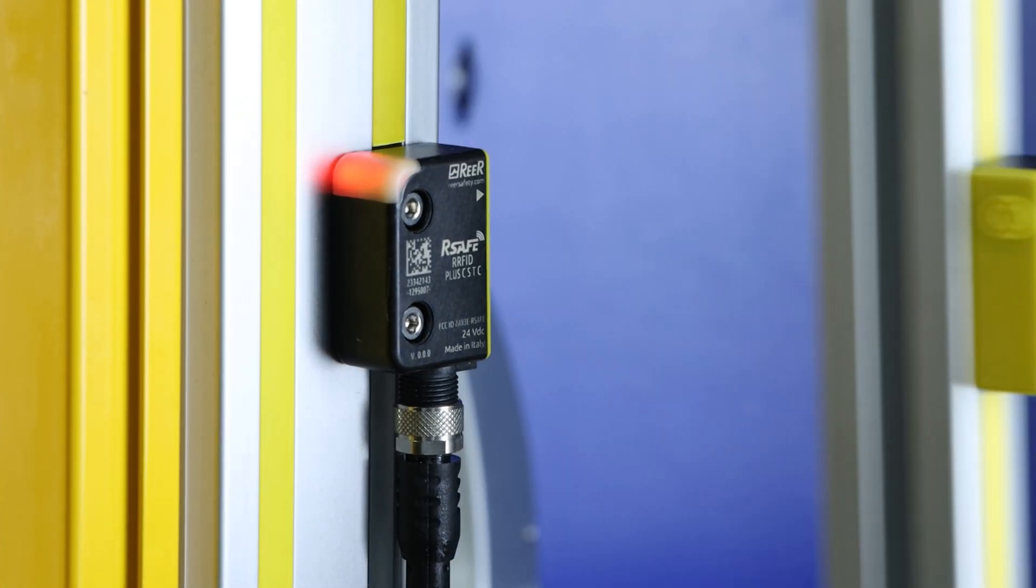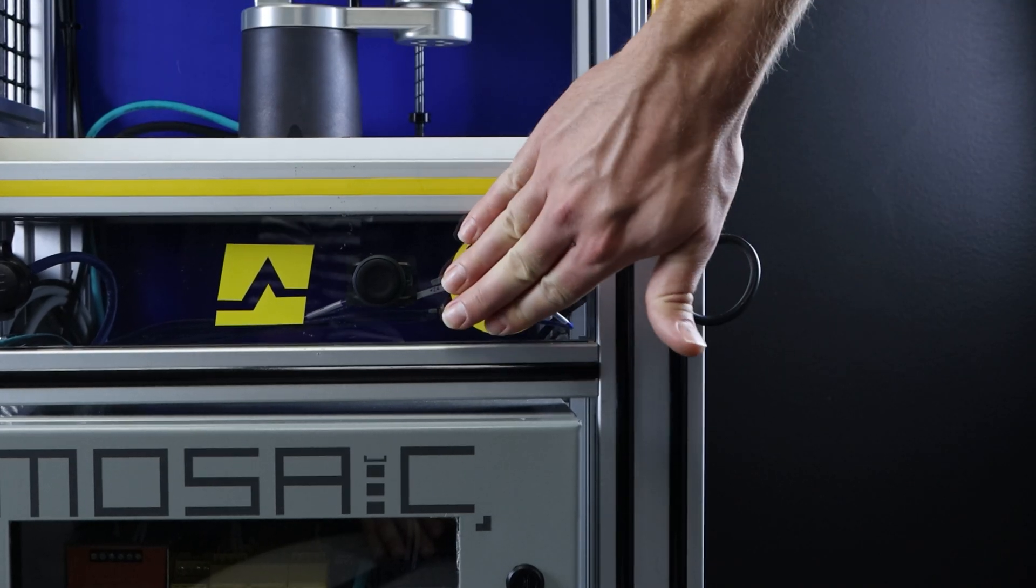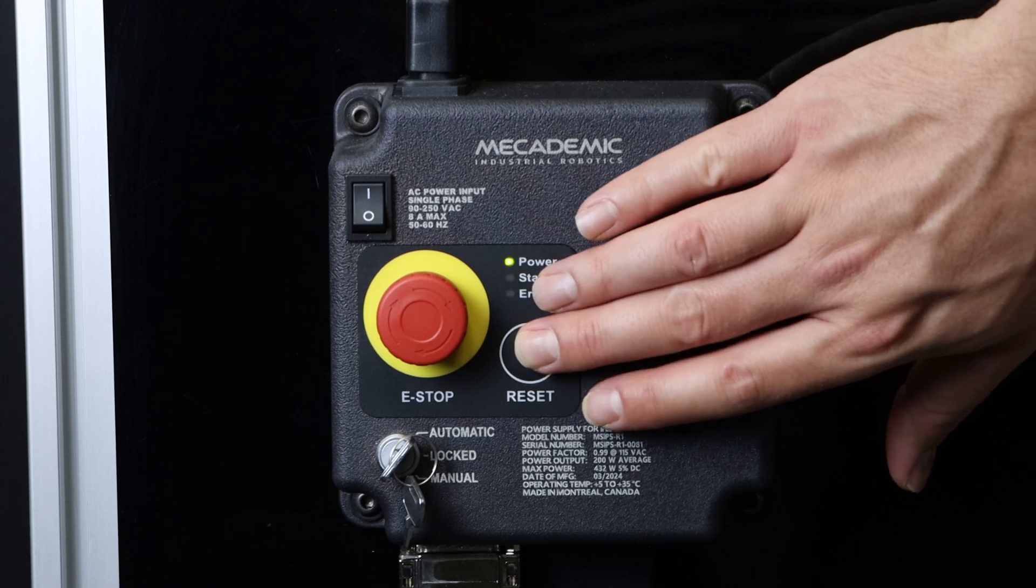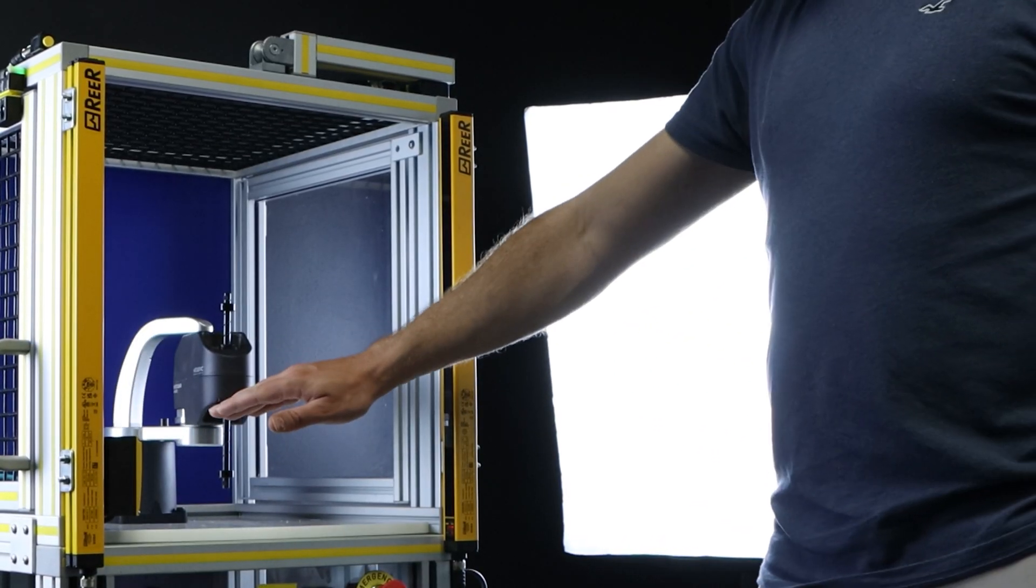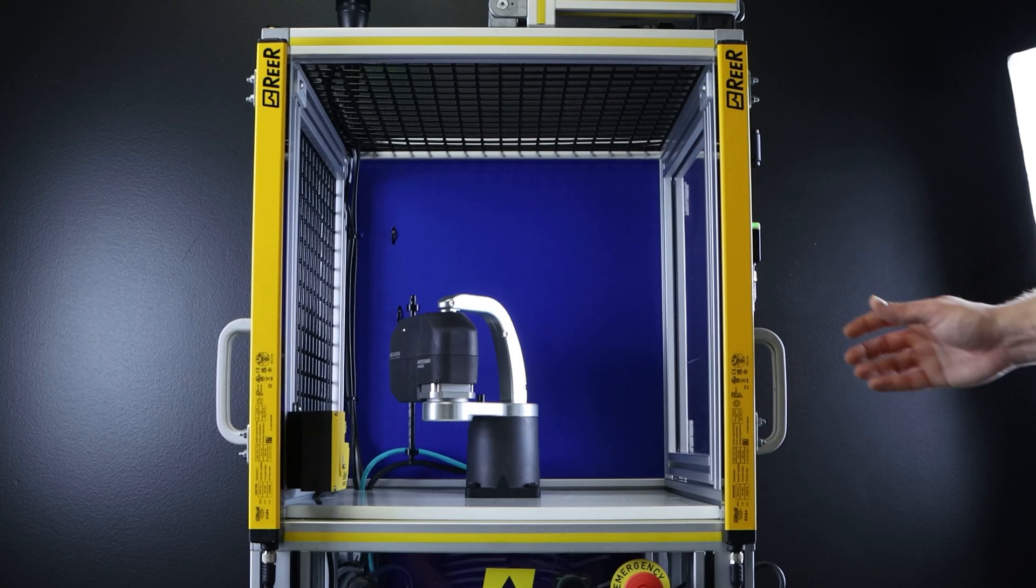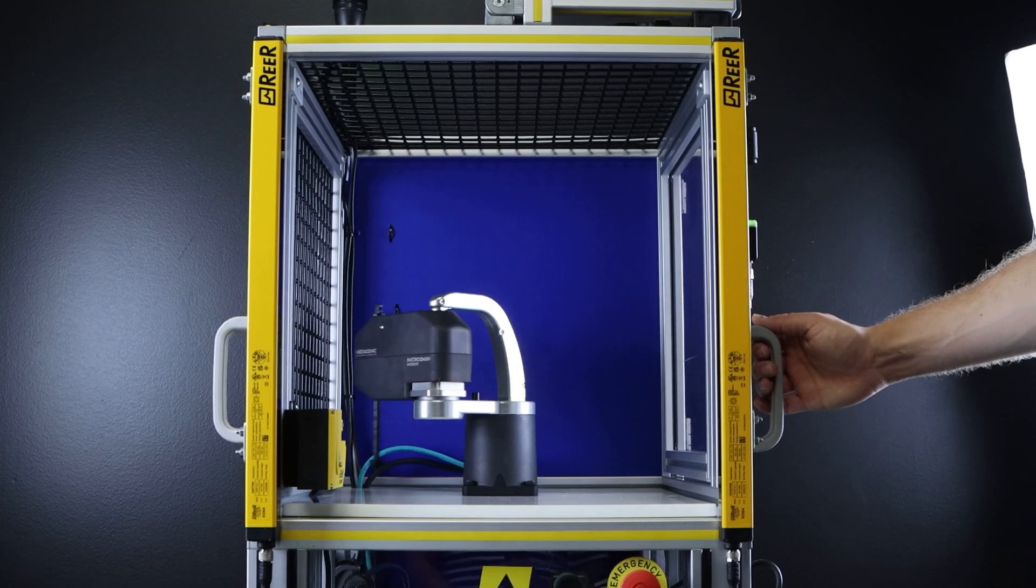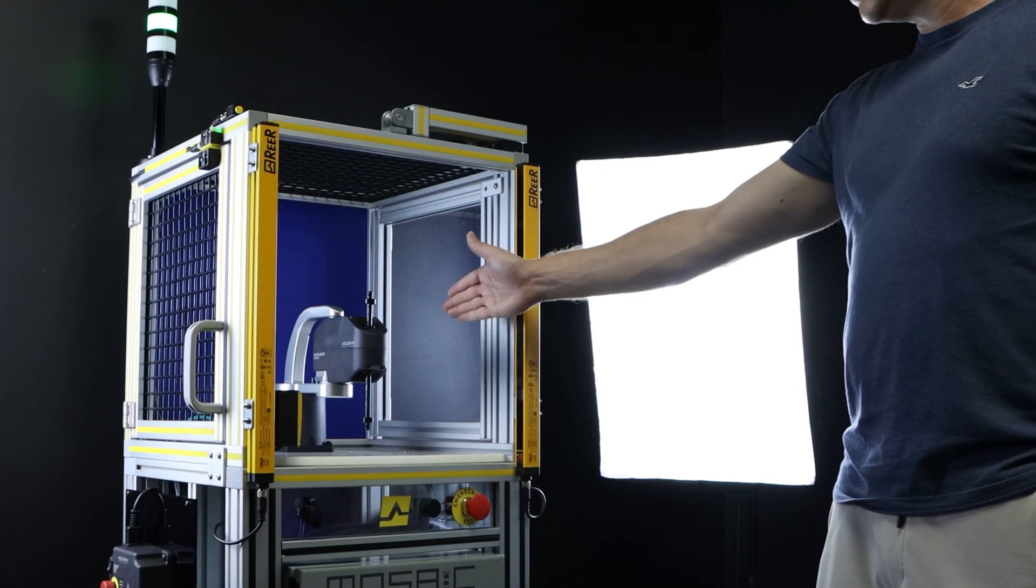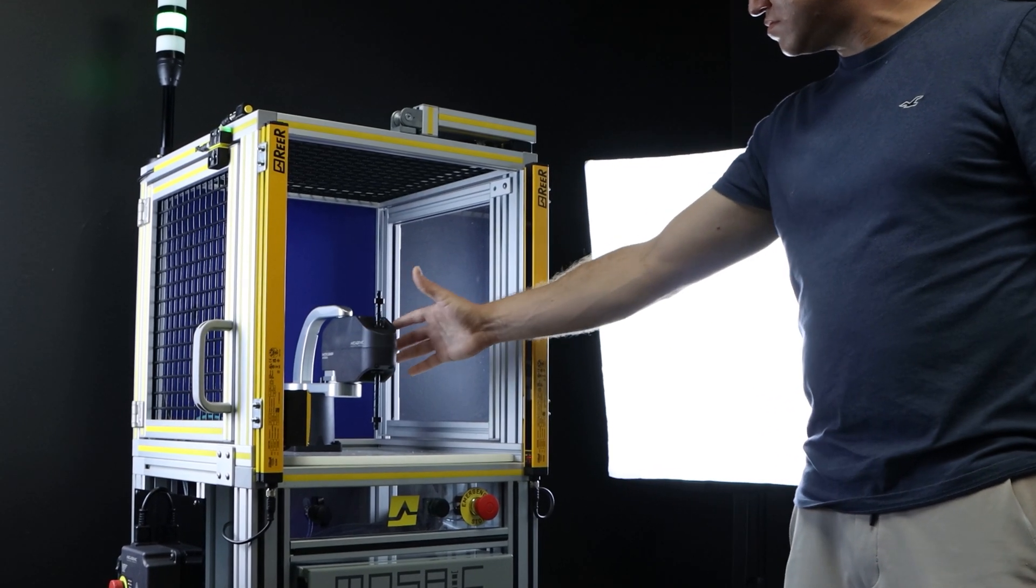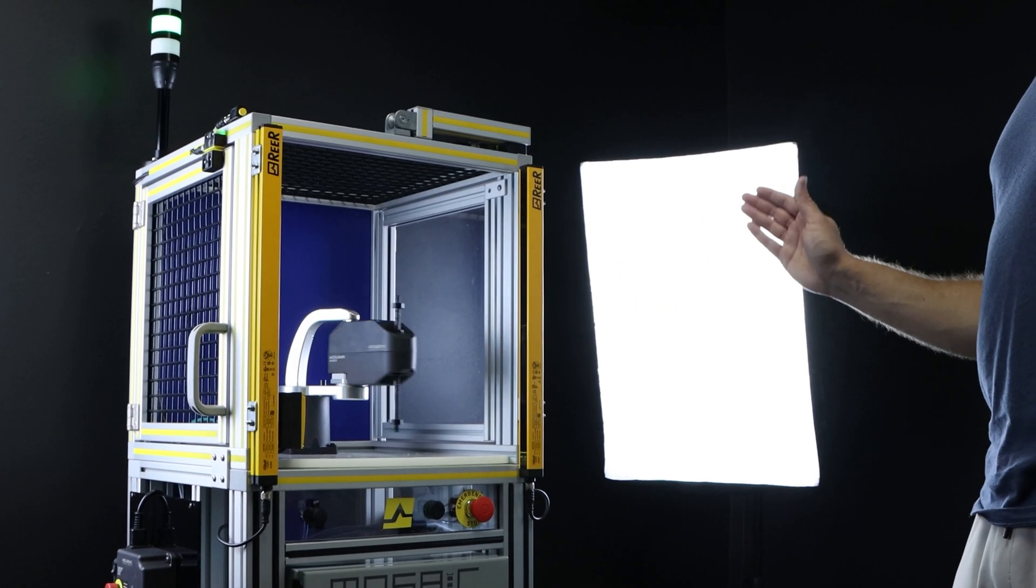If an emergency stop is triggered, the robot will halt immediately, requiring a reset to continue. Both doors and light curtains enhance safety. Opening a door activates a safety stop, while the light curtain will pause the robot but allow it to restart automatically after clearance.